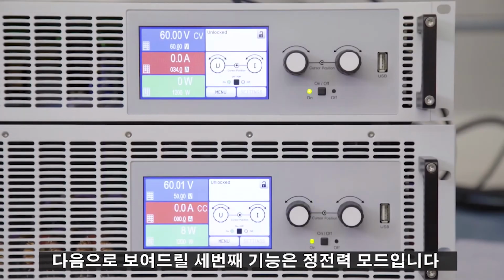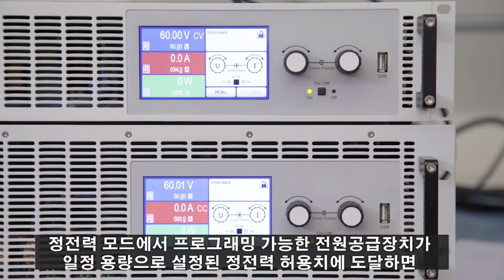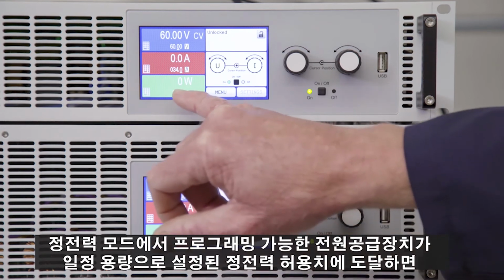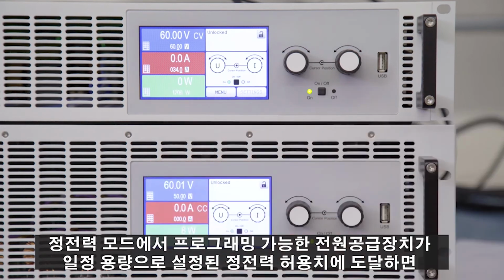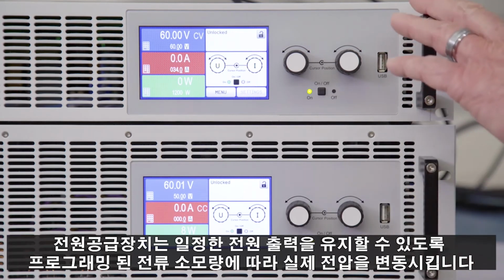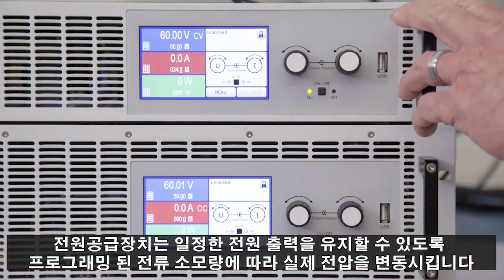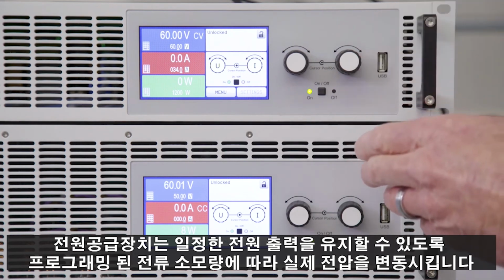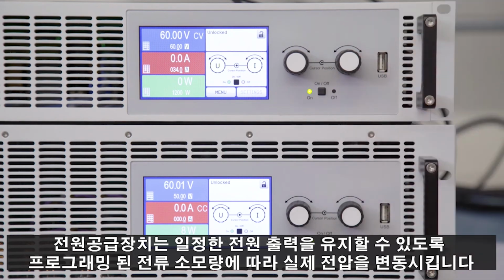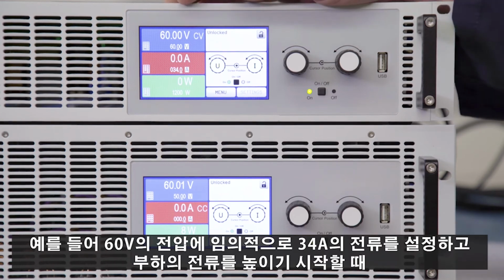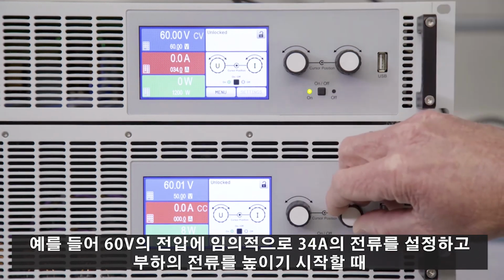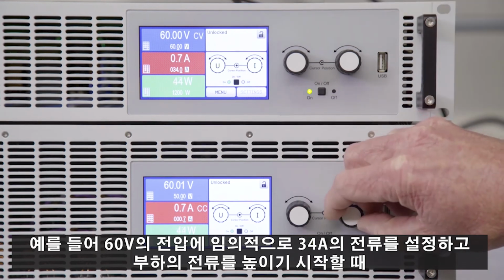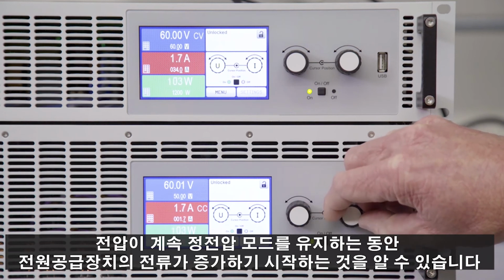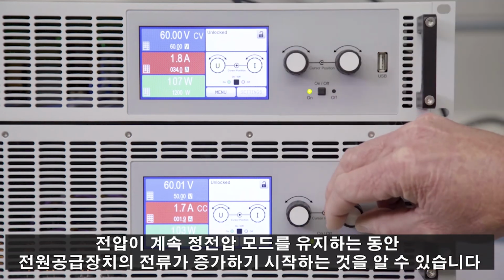The third mode of operation that we're going to show you here is what's called constant power mode. In constant power mode, once the programmable power supply reaches its programmed constant power limit, the power supply will actually fluctuate the voltage based on the current draw that's programmed to be able to maintain a constant power output. Here, we set up 60 volts and an arbitrary 34 amps of current. As I start to increase the current on the load, you'll notice the current on the power supply starts to increase while the voltage is still maintaining in constant voltage mode.